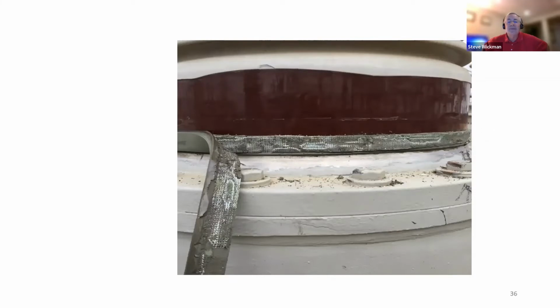And you're looking, so what's that funny meshy stuff there? Well, in this installation, they had put a piece of fiberglass mesh around the perimeter of the bushing, just to help hold that clamp in place so it didn't hike up as the sealant compound was injected into it. And again, that can be easily cut away if need be for whatever they might be doing.